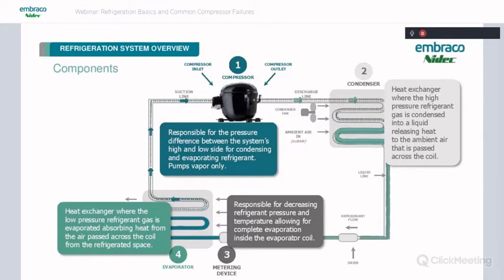And so we're going to absorb all that heat in the evaporator, and then it's going to come down as a vapor through the suction line back to the compressor, where the cycle is going to start all over again. And one thing to note is the condition of the refrigerant through the system. As you can see, going into the compressor, it's low pressure suction vapor, and coming out, it's high pressure discharge vapor. And then it's turned into a liquid after the condenser. So you can kind of see the state of the charge of the refrigerant as it goes through the system.